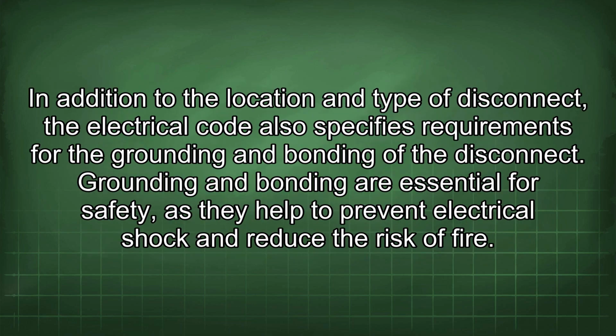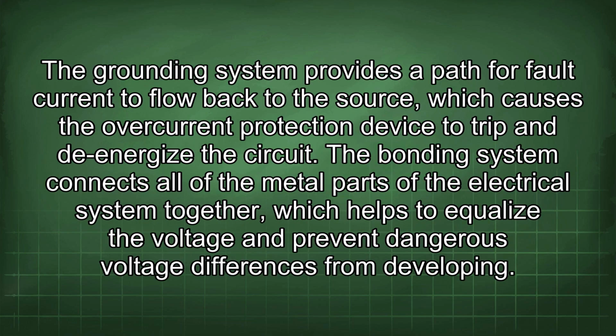In addition to the location and type of disconnect, the electrical code also specifies requirements for the grounding and bonding of the disconnect. Grounding and bonding are essential for safety, as they help to prevent electrical shock and reduce the risk of fire. The grounding system provides a path for fault current to flow back to the source, which causes the overcurrent protection device to trip and de-energize the circuit. The bonding system connects all of the metal parts of the electrical system together, which helps to equalize the voltage and prevent dangerous voltage differences from developing.